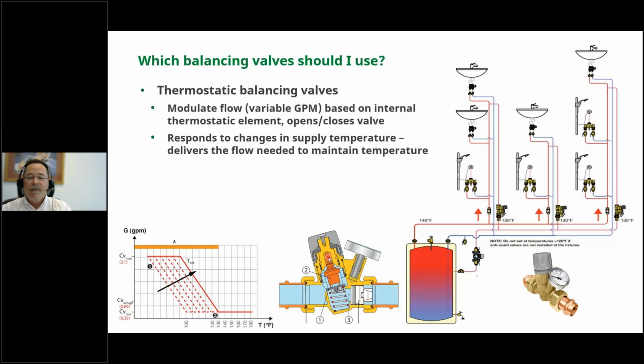In this cross section, we happen to show one that has a check valve and an insertion temperature gauge. This is what that one looks like in a photograph. So it responds to changes in supply temperature and delivers the flow needed, whatever that flow is, to maintain temperature. And if you think about it, we're really interested in just temperature. That's all we want. We want hot water at these fixtures. We don't really care about differential pressure or GPM. We just want the temperature to be consistent. So that's why these are so nice, is they get right to the point.